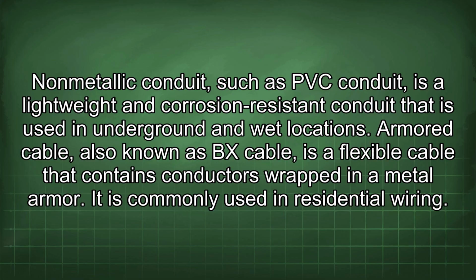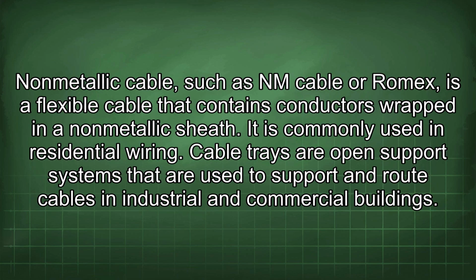Armored cable, also known as BX cable, is a flexible cable that contains conductors wrapped in a metal armor. It is commonly used in residential wiring. Non-metallic cable, such as NM cable or Romex, is a flexible cable that contains conductors wrapped in a non-metallic sheath. It is commonly used in residential wiring. Cable trays are open support systems that are used to support and route cables in industrial and commercial buildings.